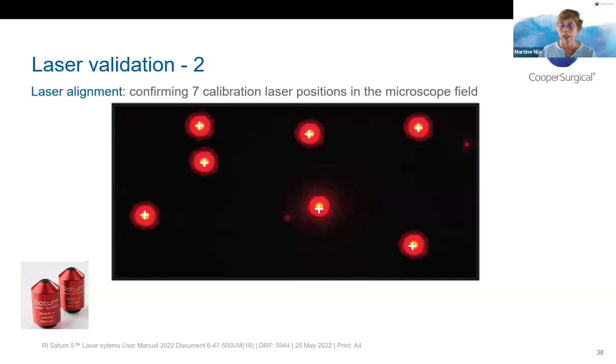So there is a link to the intensity of the laser beam, and that works with time. So a laser beam is 300 microseconds, for example, or 600 microseconds or less. And depending on the length of exposure, the size of that hole will be different.